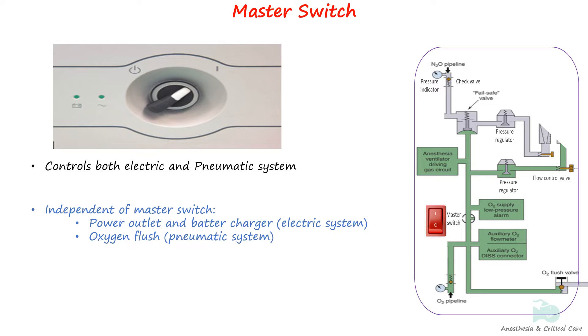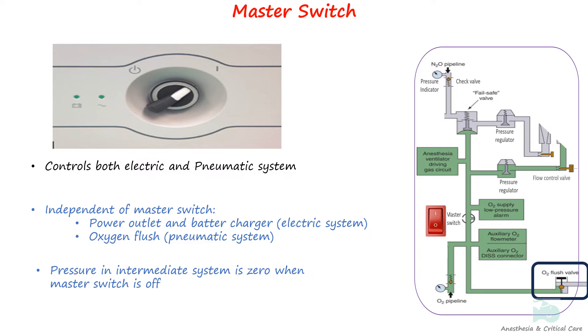The pneumatic portion of the master switch is located in the intermediate pressure system, downstream of the inlets for cylinder and pipeline supplies. It controls various components of both the electric and pneumatic systems. Electrical outlets and battery charger remain active when the master switch is off, and the oxygen flush button can also be activated independently without turning on the master switch. When the master switch is turned off, the pressure in the intermediate system will drop to zero.